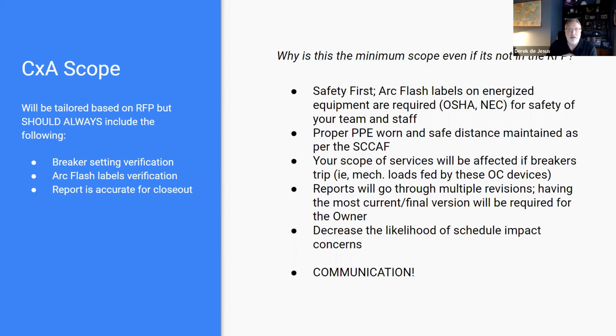So contractors typically will work within and under a temporary arc flash label, which will carry bare minimum requirements for PPE, but also it'll carry the requirements that only the electrician and or qualified staff can enter and work within that space. So let's take a pause there. You, as the commissioning agent, working on a mechanical piece of equipment that serves an electrical room, need to be aware that if you're working in or around that electrical vault or that electrical room that is energized, you should also be wearing or be prepared to wear that PPE if people are working in that electrical equipment, right?